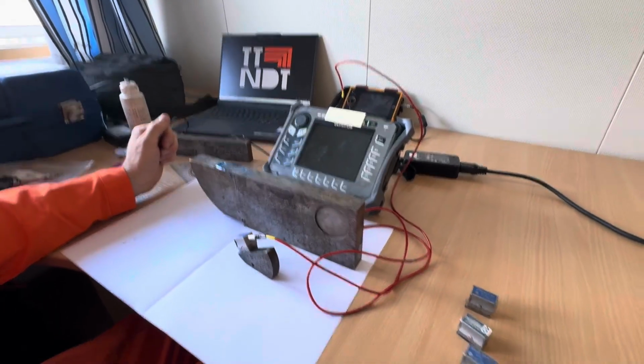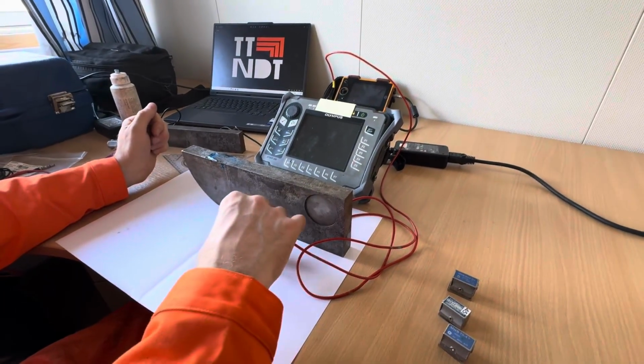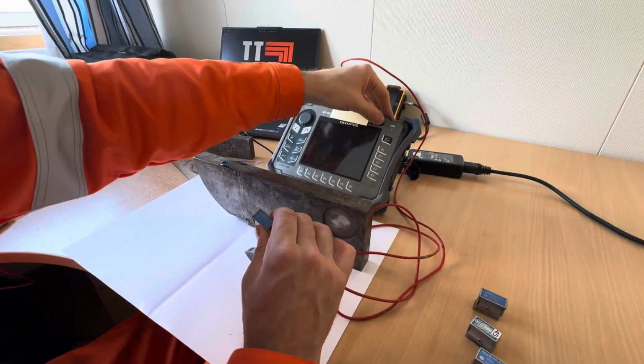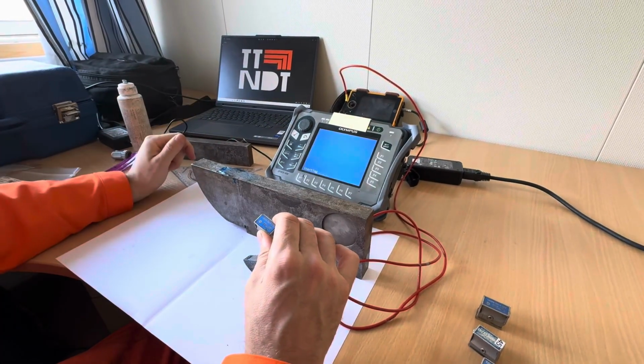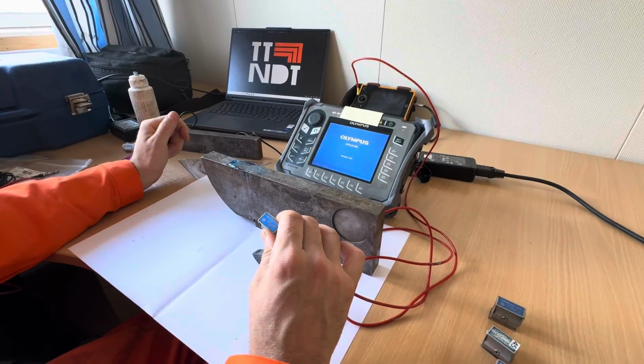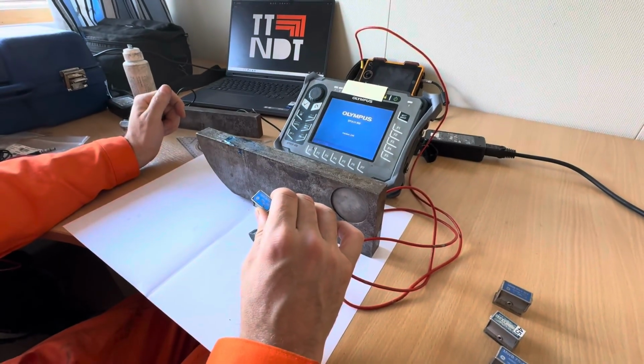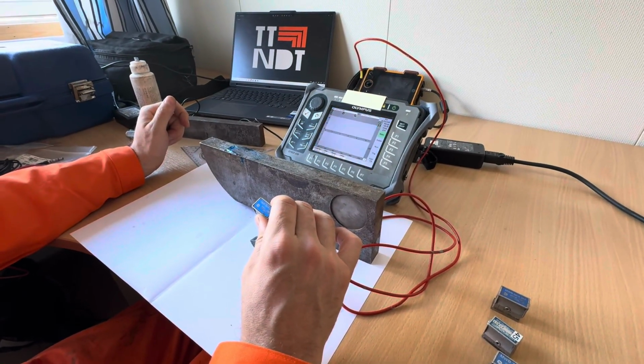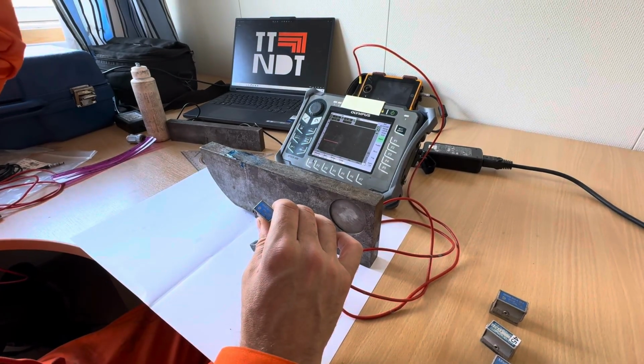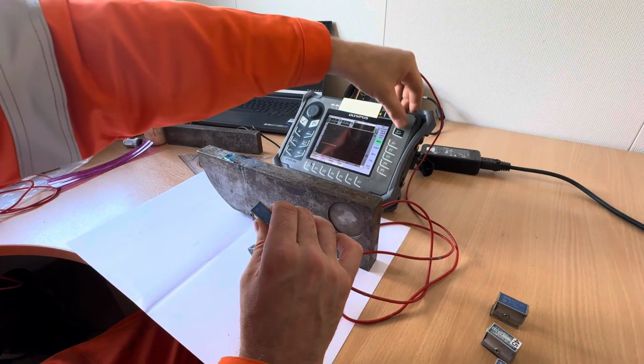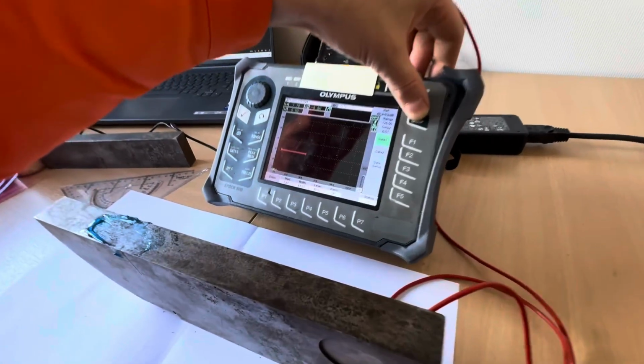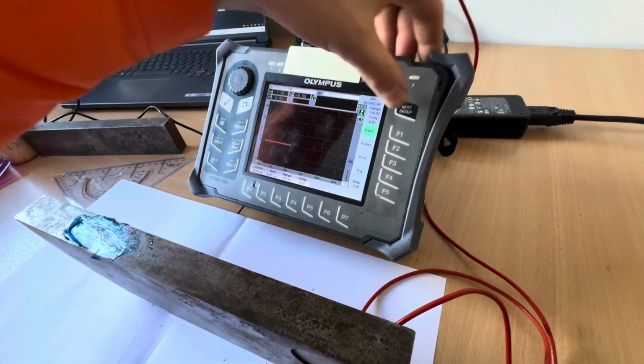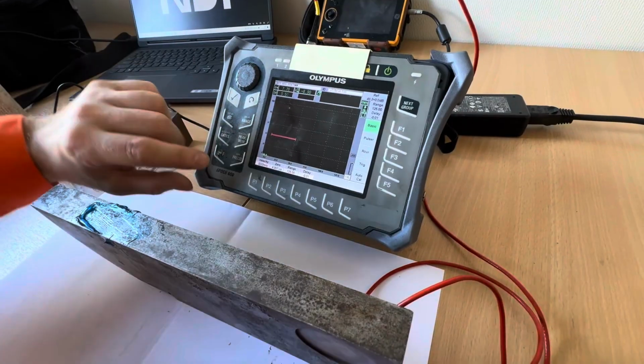Now I'll show you how to perform auto-calibration for an angle probe, 60 degrees. Turn on the device. This will be the Olympus 600. The main function that will be used to navigate through all the menus is Next Group. If we press Next Group, we need to find, here it says Basic.